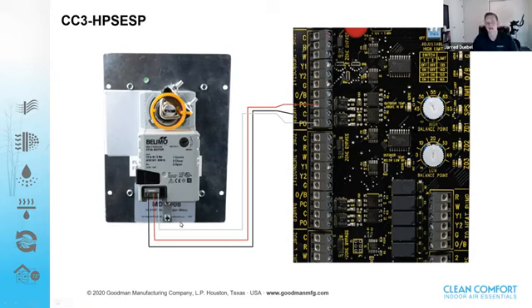And those can be what we call daisy chained or wired in series, which means if this is my primary zone 1 damper and I wanted to put several other either round or rectangular zone dampers in there, I can actually daisy chain straight from one motor to the next. Now, when it comes to installing these dampers, it says right here on the motor, and there's correlating numbers on these terminals, which wire is going to need to land where. So it says number 1 is common, number 2 is power close, and number 3 is power open. We make it very simple and put that right on our zone control panel as well. So of course you have common right here, you have power open right here, and power close right there.